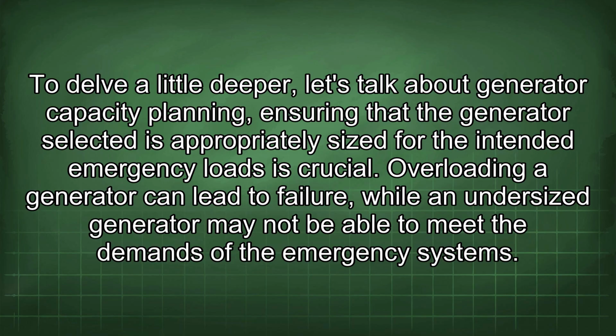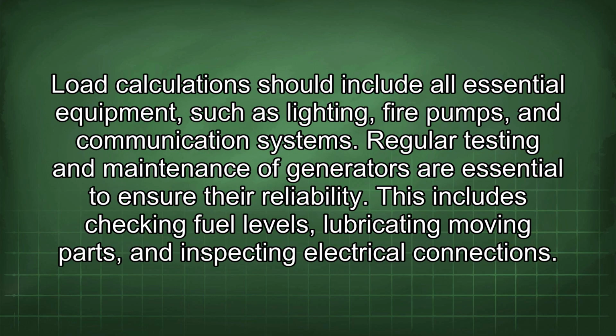To delve a little deeper, let's talk about generator capacity planning. Ensuring that the generator selected is appropriately sized for the intended emergency loads is crucial. Overloading a generator can lead to failure, while an undersized generator may not be able to meet the demands of the emergency systems. Load calculation should include all essential equipment, such as lighting, fire pumps, and communication systems.